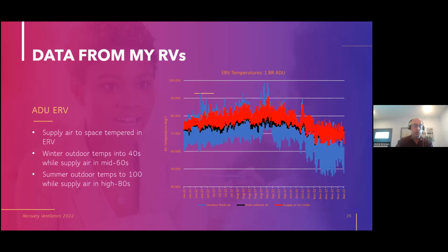Now let me show you the temperatures from those hobo monitors. The blue is the outdoor fresh air, and this is a period from June to December of 2022, so about 6 months. So you can see that in winter, we're dropping down below 50, say 46. That's right here. And in summer, we had some days up in the high 90s, outdoor air. But the red is the supply air to the inside. So can you see that in winter on these 40-ish degree days, the worst we're doing is bringing in supply air in the mid 60s, right? So that's this area under the red is the savings to our HVAC system.